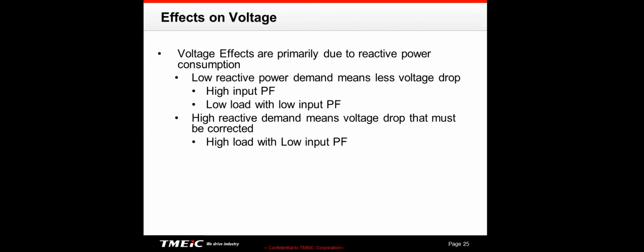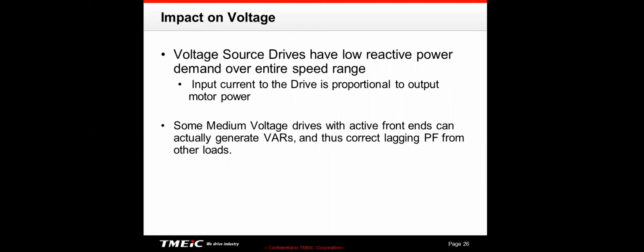Now, it's also interesting, a lot of people don't think about this, but on systems, and particularly on medium voltage systems, your voltage drops are primarily proportional to your VARs, not to your kilowatts. That's obviously not 100% true, but a higher power factor will give you better voltage regulation. So if your voltage is up and down quite a bit and you increase the power factor, then you will improve your voltage regulation. Your voltage now will be tighter, and that will help everything in your plant, help your motors, help your loads, help everything.